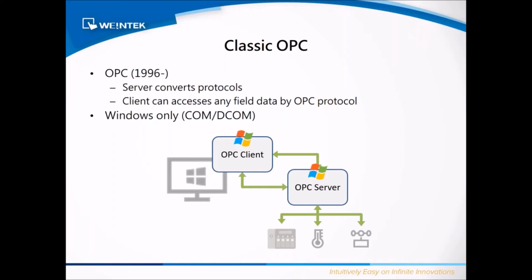How you use it is that you have one OPC client talking in the OPC protocol to an OPC server, and the OPC server will help you translate different machine languages into OPC language. So the OPC server is the one that translates every machine protocol into the OPC protocol. And the client, or the graphic interface that you are using, is the OPC client.